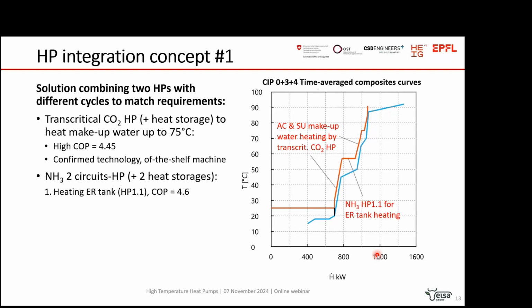And one solution to provide heat to the tanks, the recycled water tank and the acid tank, could be ammonia with 2 circuits, a 2-temperature heat pump, of course also with 2 storages, for the reason I showed just before. One would have a rather high COP for heating the recycled water, and the second a lower COP but also a lower contribution.